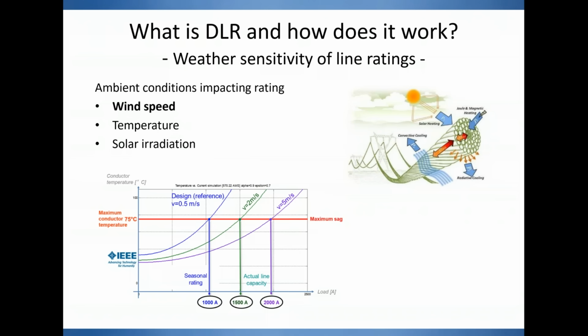Typically, the rating would be determined assuming very low wind speed, typically 0.5 meters per second. The different standards, either IEEE standards or CIGRE standard, are very, very similar. So that would result in this example in a capacity of, say, 1,000 amperes. Now, if you assume that the wind blows at only 2 meters per second, then you can see that the curve moves to the right-hand side, and therefore the capacity increases by 50%. If the wind blows at 5 meters per second, which is normally the type of wind that you see, which starts to activate wind turbines, the capacity doubles.